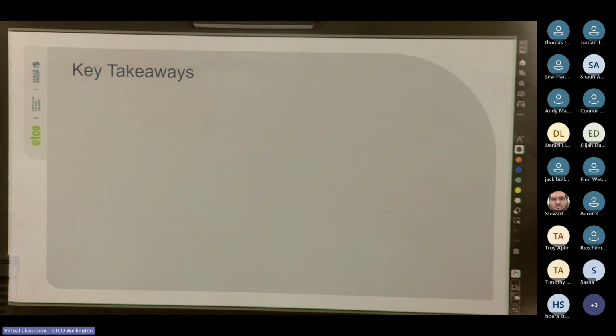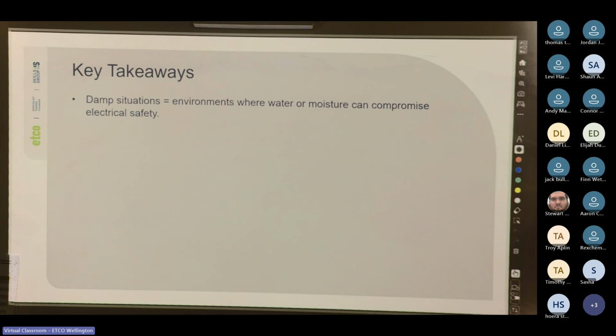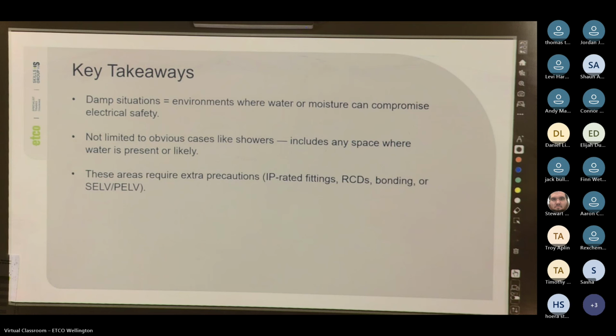Cool. So some key takeaways from what we've talked about so far. Damp situations equal environments where water or moisture can compromise electrical safety. It's not limited to the obvious, like showers. It includes any space where water is present or likely. So these areas require extra precautions, so IP-rated fittings, RCDs, bonding, or safety extra low voltage or protective extra low voltage. These are the kind of things we need to take into consideration when we're looking at damp areas.